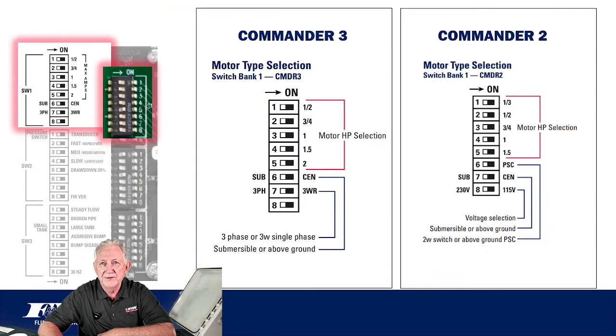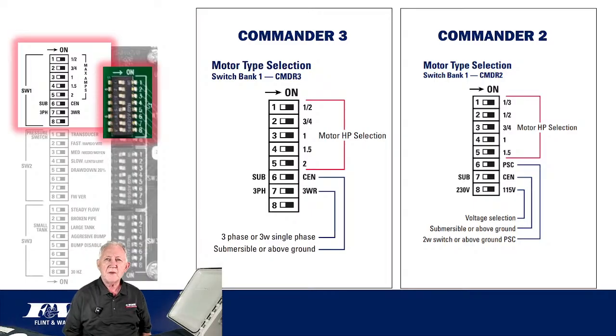Now here's the differences between the Commander 2 and the Commander 3. That Commander 3 on the left-hand side of your screen, that's the one we just talked about, where you've got your horsepower listed at the top, and then you've got a choice between a submersible and a centrifugal, 3-phase or 3-wire. If you move to the right, this is going to be on a Commander 2. This is a 2-wire motor drive, and if you look, this is only going to go to 1.5 horses, because that's where we stop with 2-wire motors.